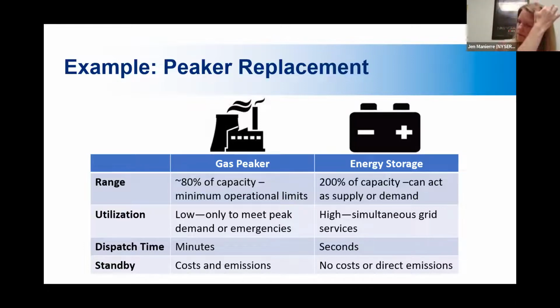So peaker plants. When the grid is operating, we have base load power plants that are essentially running all the time at a fairly high capacity, just generating electricity that goes wherever it's needed. And for the most part, that serves our needs. But on those really hot summer days when everyone's turning on their air conditioning, people are still at work, but also people are coming home from work. So the lights are on in both places, the air conditioning is on in both places. That's a time of peak electricity demand on the grid. And the way we've traditionally dealt with it is through gas peaker plants. They'll only fire up when needed for these short windows of time, call it between 4 and 6 p.m.